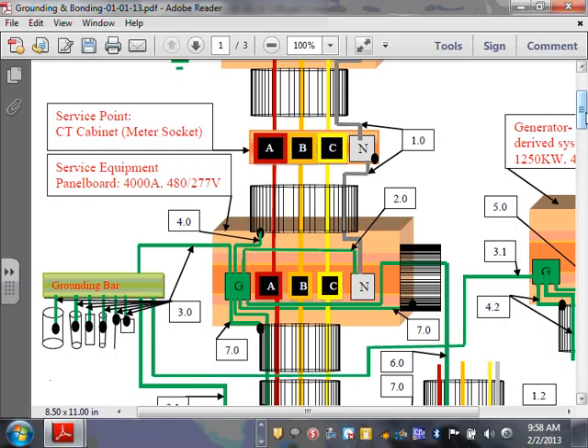Okay, we're inside the switch gear. We brought our 277 and neutral. We brought our three-phase 480/277. Now, the first thing we do is switch gear. You're going to have a bus bar, 3 bus bars for the phases, horizontal or vertical, depending on your switch gear or switch board or panel board. You're going to have a neutral bus bar and a ground bus bar in the bottom of your switch gear. If it's a 200 amp panel, you're going to have the same 2 bars.